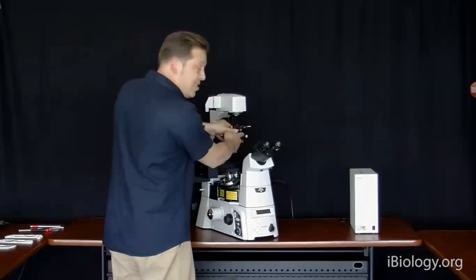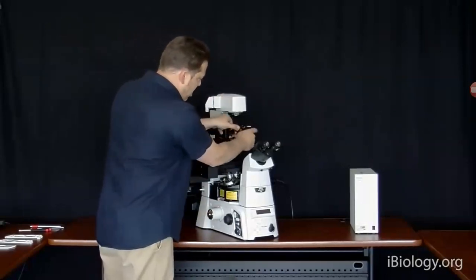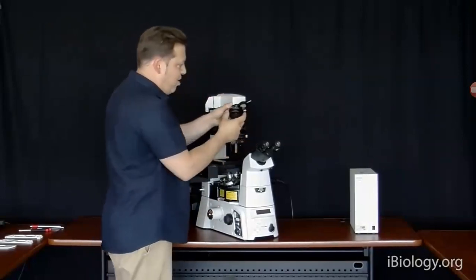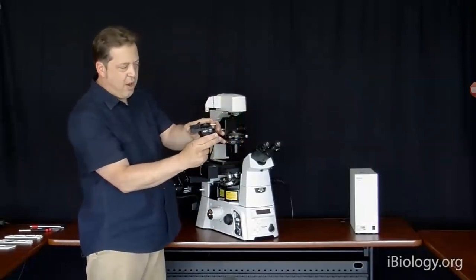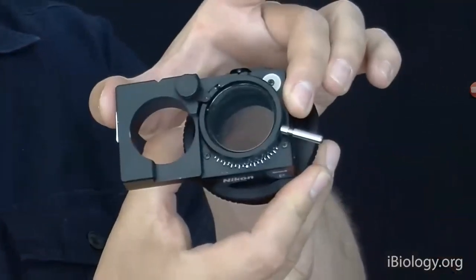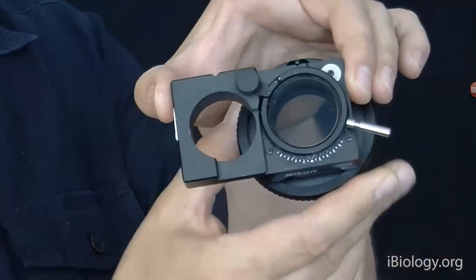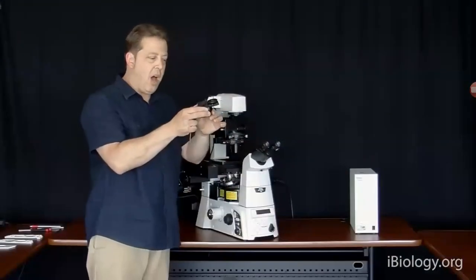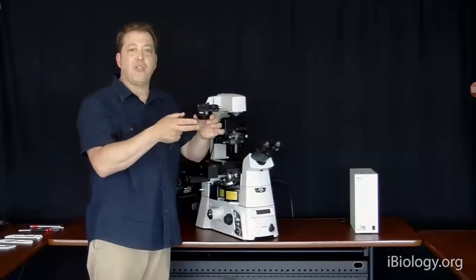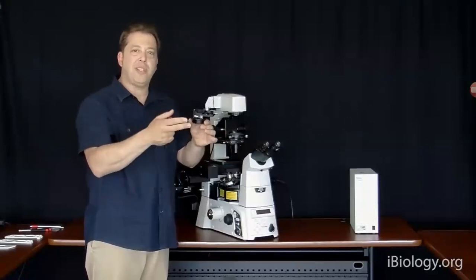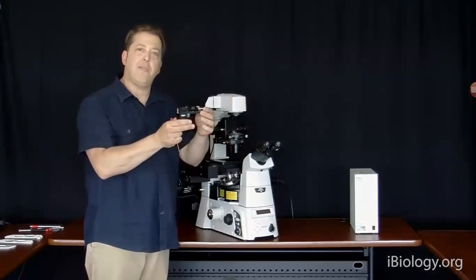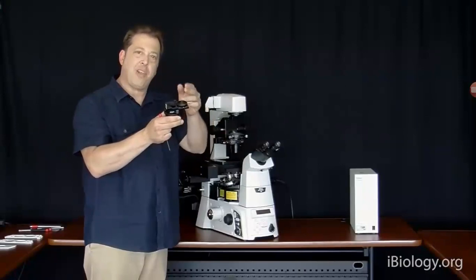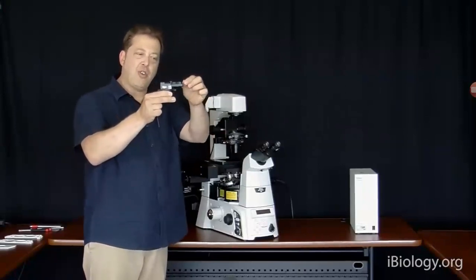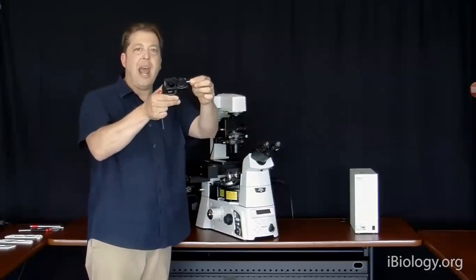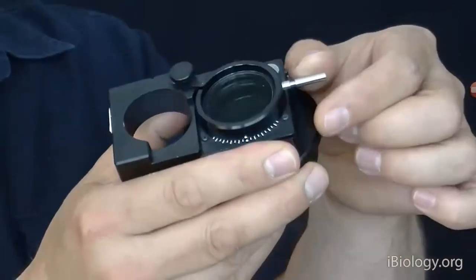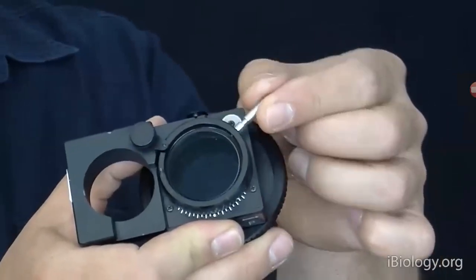Below that, we have the condensing system of the transmitted light path, and we'll start with this polarizer here, which is held on with one screw. This is a polarizer that can go in or out of the light path. This is also the compensator of our differential interference contrast system. When you have differential interference contrast, there are many different ways that you can adjust or compensate for the contrast. We use what's called the de Sénarmont compensation, and in that case, we would have a quarter wave plate and polarizer sandwiched in this device, and you can rotate the polarizer relative to the quarter wave plate. That allows you to adjust the shadowing or contrast of the differential interference system and also change the directionality.